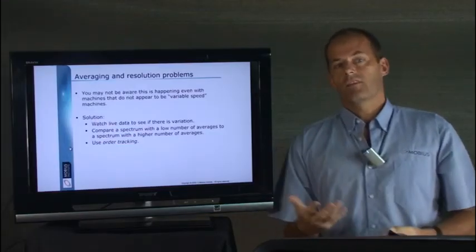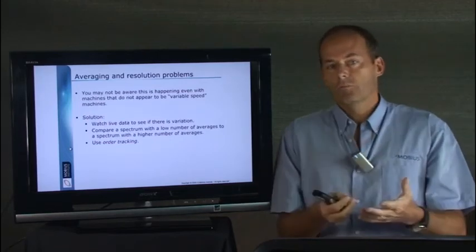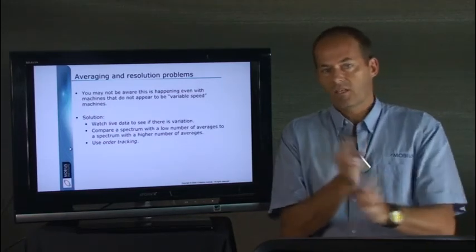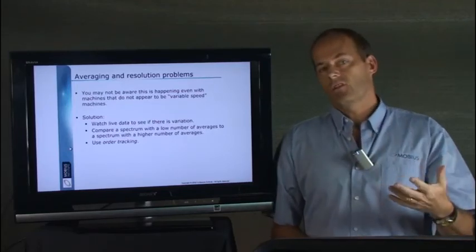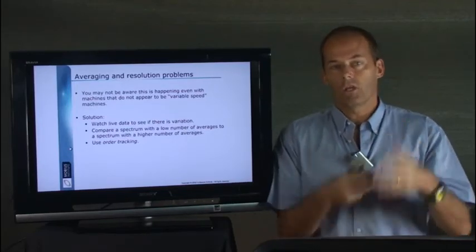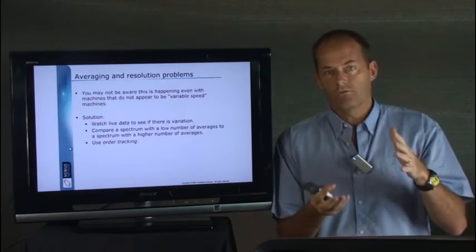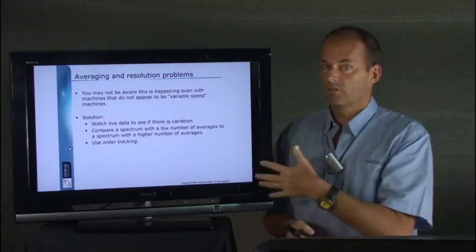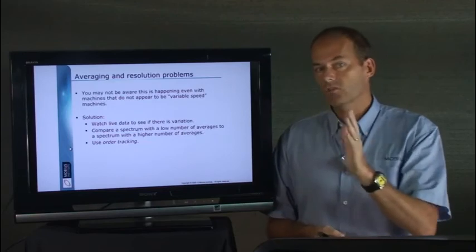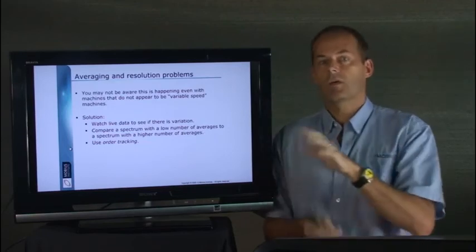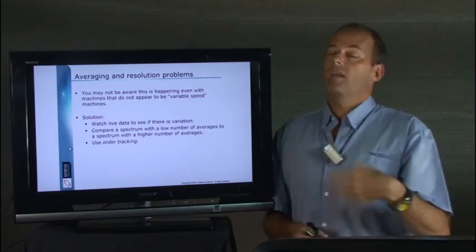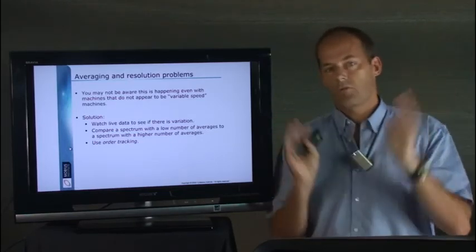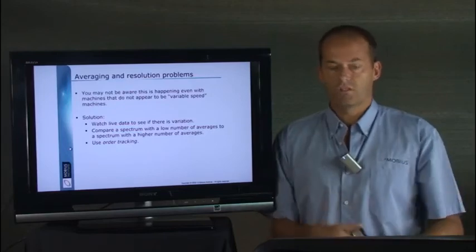You may not be aware that this is happening. I mean, with a variable speed process where the speed is varying, it should be something you're aware of. It may be something that you think, look, it'll be fine. You know, it seems fairly constant when I'm testing it, but this is what's happening. If it's varying very much, particularly those high frequencies, remember, they'll smear and they will drop down. They may be repeatable, but they just don't represent anything about the true condition of the machine.